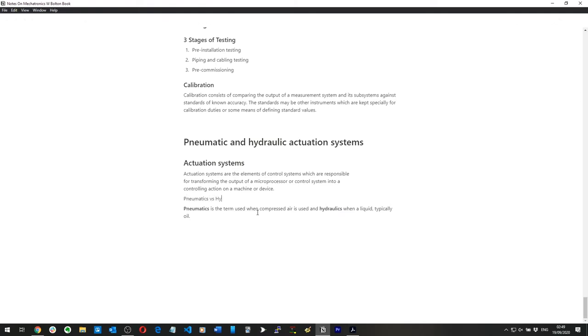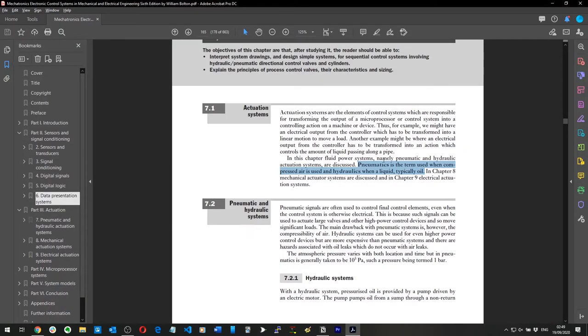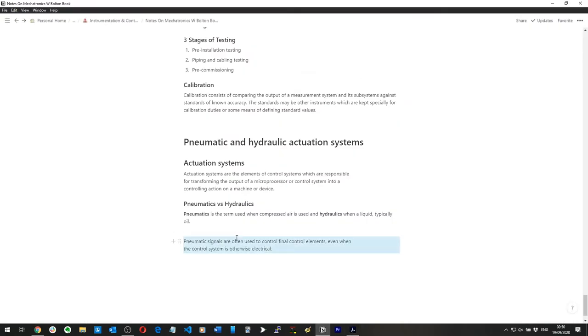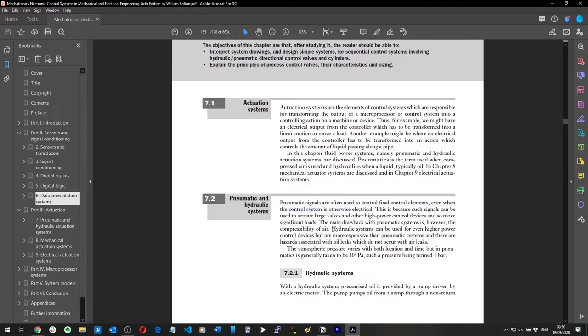Pneumatic signals are often used to control final control elements, even when the control systems are electrical. Hydraulic systems can be used for even higher power control devices, but are more expensive than pneumatic systems, and there are hazards associated with oil leaks.